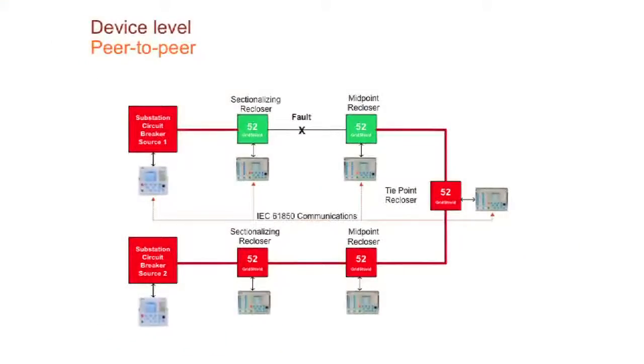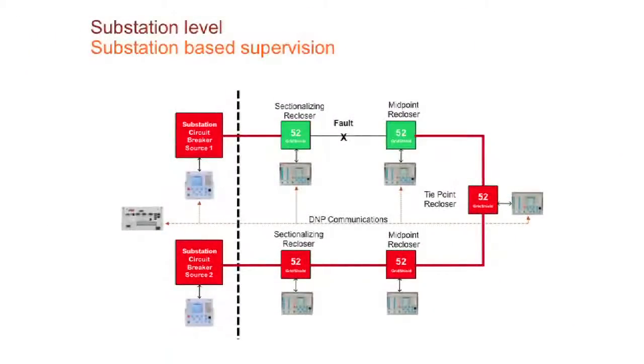It sends a signal upstream to disable your pickup, your 50P, because for coordination, once you put in distributed generation, coordinating a lot of reclosers becomes really hard. So what they found is that they can do the feeder coordination by just blocking. If this one picks up the fault, it automatically blocks the fast overcurrent elements on the upstream device. So it helps you improve feeder coordination, because it becomes really tough once you start adding a lot of devices out there. This is one of the things I was talking about. One of the challenges is obviously reliability. You have the recloser, but also supporting emerging energy sources like distributed generation, wind farming in this case. So you work on the reliability, but also on supporting a lot of these emerging trends.